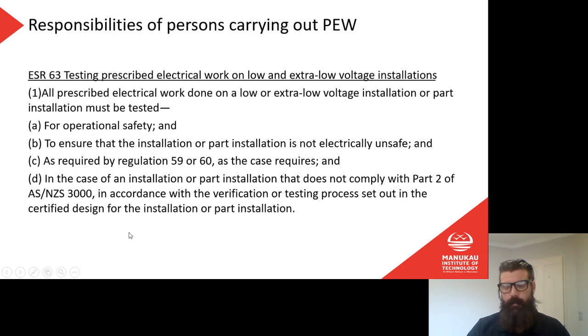Right, so that last bit there is saying that if we do an installation that doesn't comply with Part 2 of AS/NZS 3000, we talked about that in the previous topic, what Part 1 and Part 2 meant, and again, just to be clear, we're almost always working under Part 2. It's very, very rare that we're going to come across work that we do under Part 1 only, or that does not comply with Part 2. This is saying that if we're not complying with Part 2, we have a certified design for that installation, and that certified design will contain procedures for the testing, verification and safety of that installation. So if we have that verified design, then we have to do our testing in accordance with that design.